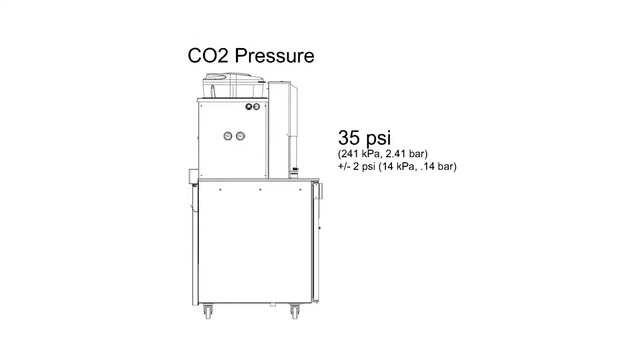We would suggest that you check your CO2 pressure. If your CO2 pressure is not where it should be, you should adjust the pressure to make sure that it is. It should be at least 35 psi on the gauge on the left side of the machine.